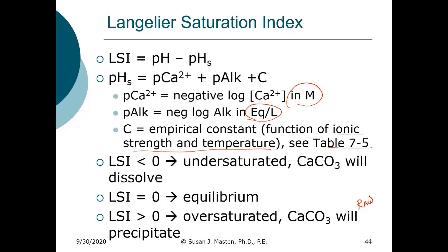The treatment that was used in Flint, which included ferric chloride coagulation and lime softening, resulted in a treated Flint River water that had an LSI that was significantly negative. And when I mean significantly negative, negative 1.5 and greater.